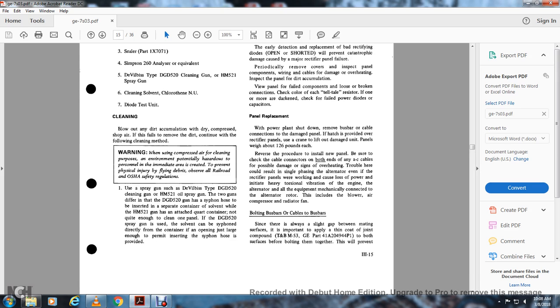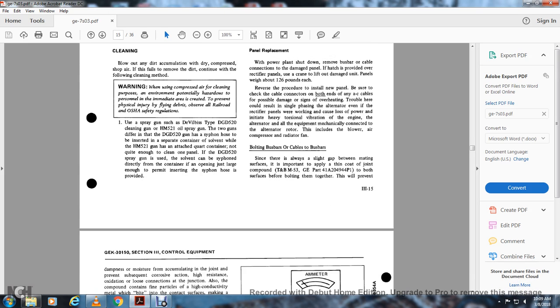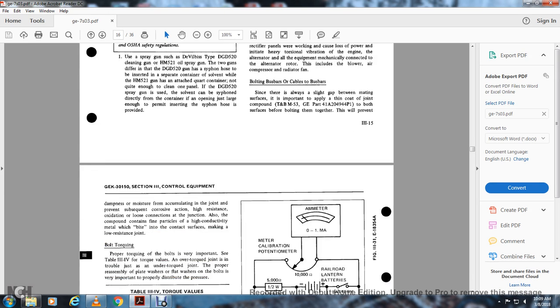there's always a slight gap between the mating surfaces. It's important to apply a thin coat of joint compound T&B M-53, GE part 41A204944P1 to both surfaces before bolting them together. This will prevent dampness and moisture from accumulating in the joint, preventing subsequent corrosive action, high resistance oxidation, and loose connections at the junction. Also, the compound contains fine particles of a high conductivity metal that bite into the contact surface, making a low resistance joint.